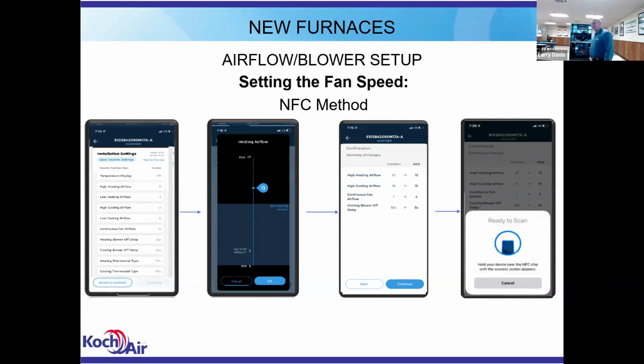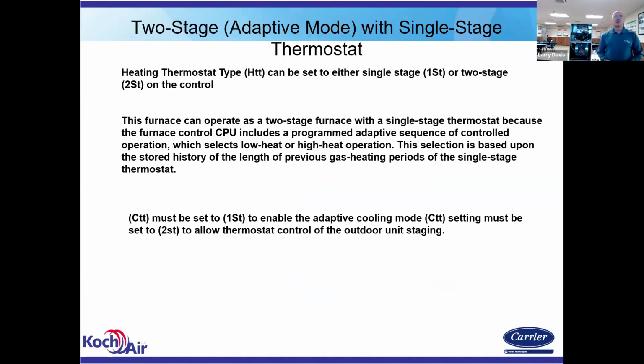Okay. So let me back up a little bit. Once you connect to that board and pull that information up, you can walk away. You've not made any changes yet to that board, and you don't have to stay right at it. You can go sit down somewhere, make the changes you want to make, and then go back and reconnect it and download that information to the board. Okay. Here, I just talked about this a minute ago. You tell it whether you're using a single stage or a 2-stage thermostat for heating and cooling. You can do a 2-stage heat, 1-stage cool thermostat. It'll work just fine. You just got to let it know what it's dealing with.